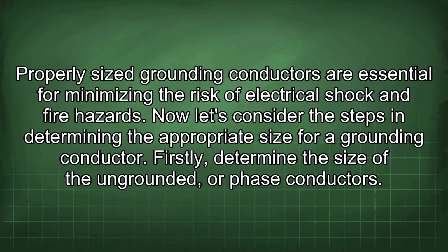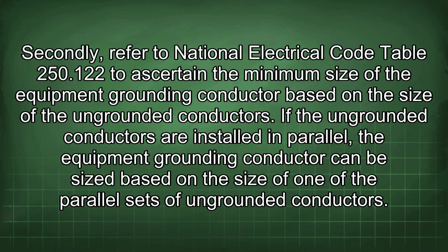Now let's consider the steps in determining the appropriate size for a grounding conductor. Firstly, determine the size of the ungrounded, or phase conductors. Secondly, refer to National Electrical Code Table 250.122 to ascertain the minimum size of the equipment grounding conductor based on the size of the ungrounded conductors. If the ungrounded conductors are installed in parallel, the equipment grounding conductor can be sized based on the size of one of the parallel sets of ungrounded conductors.